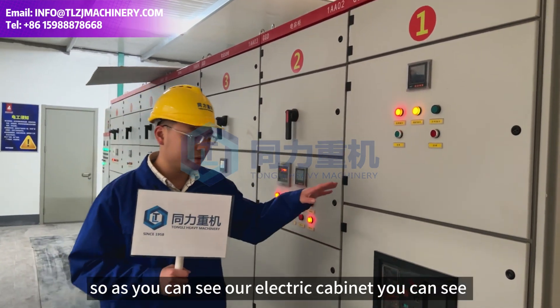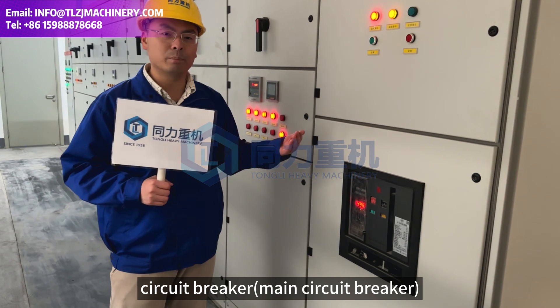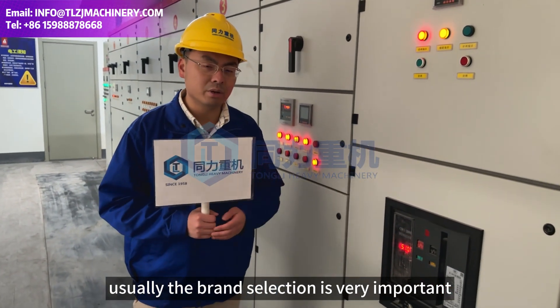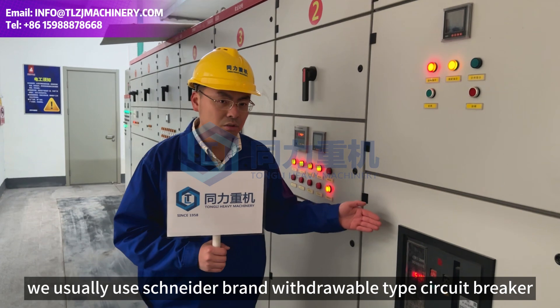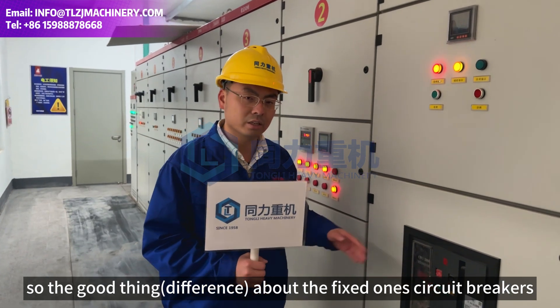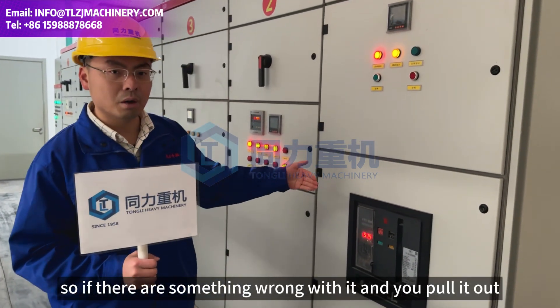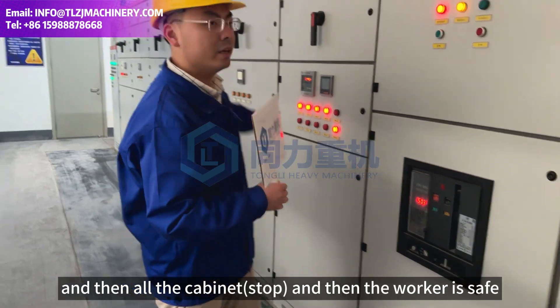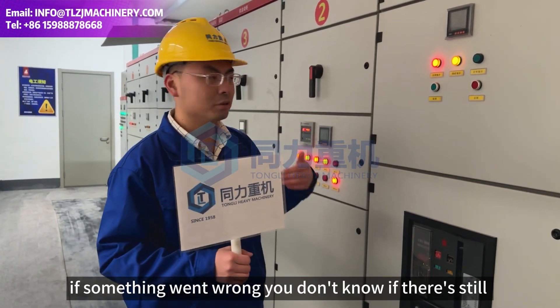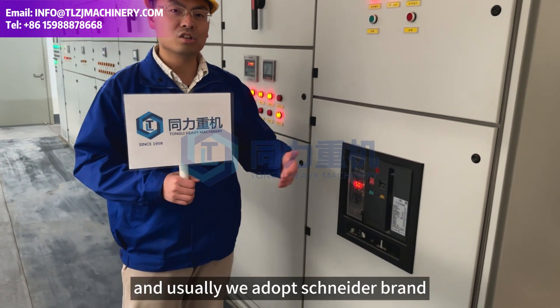So as you can see, our electric cabinet uses withdrawal type circuit breakers — main circuit breakers. For our exporting projects, brand selection is very important. We usually use Schneider brand withdrawal type circuit breakers. The advantage of withdrawal circuit breakers over fixed ones is that they are safer. If something goes wrong, you pull it out and the cabinet and workers are safe. With a fixed one, it's hard to determine if something went wrong — you don't know if there's electricity running inside. Therefore, a withdrawal circuit breaker is safer, and we use the Schneider brand.